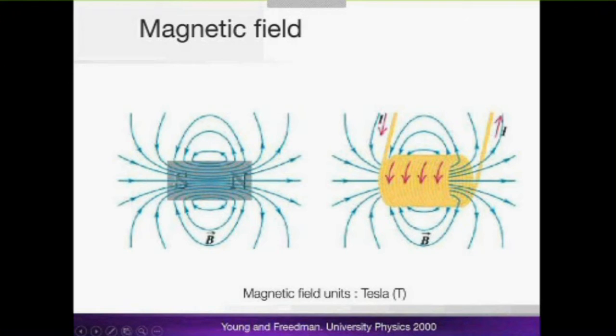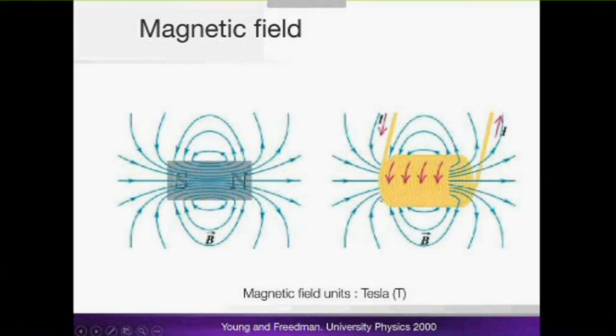You can create this magnetic field with a permanent magnet like the one you put on your fridge, but you can also induce the same magnetic field with an electric current through a coil. If you apply an electric current to a coil, you create the same magnetic field. In most MRI machines it is done this way — around the MRI tunnel there is a very large coil. Only a few systems, called MRI with permanent magnet — for example for intraoperative use — use the other type.